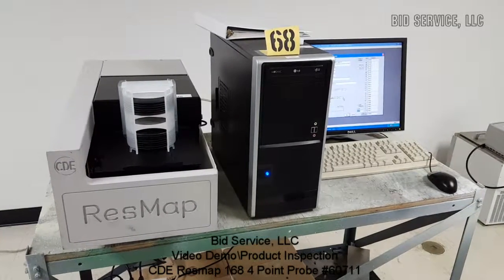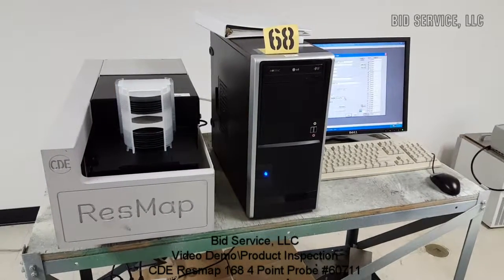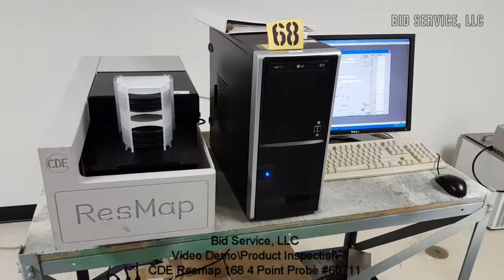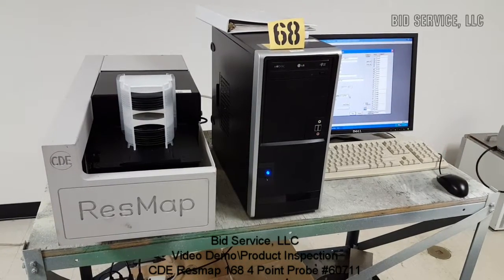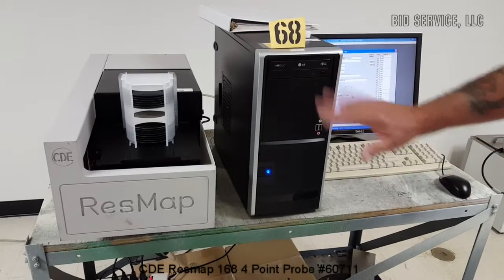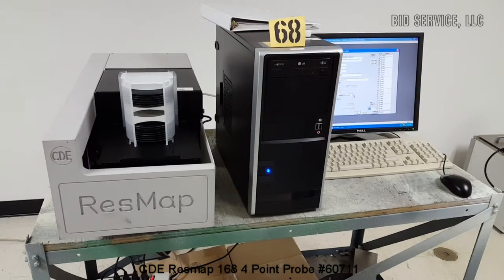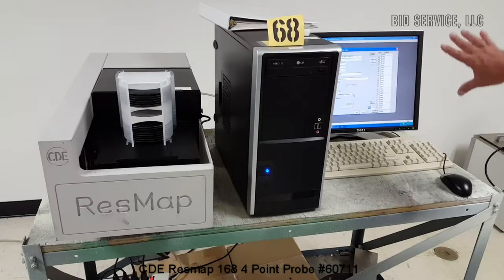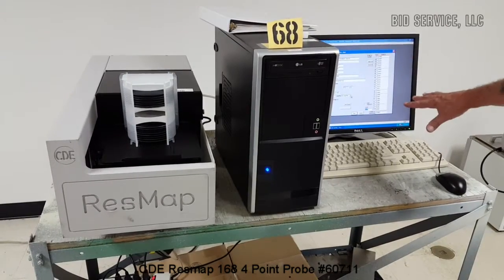This is a CDE Resmap 168. It's a wafer resistance mapper. I've got a cassette of wafers loaded. I'm going to show you one, and it's at position one. I've got it all set up already, so with that it'll go there.